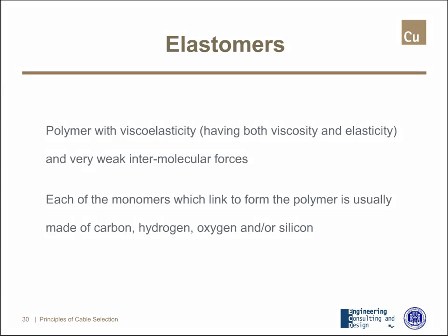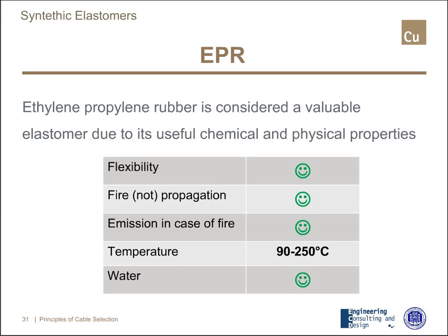Elastomers are polymers having at the same time viscosity and elasticity, characterized by very weak intermolecular forces. The most common synthetic elastomeric material used to manufacture cables is ethylene-propylene rubber. Practically all the characteristics we listed are good: flexibility good, fire propagation good, emission in case of fire intrinsically good — even if we can also add additives to enhance performance. Temperature is exactly the same as PVC, and water resistance behavior is still good.